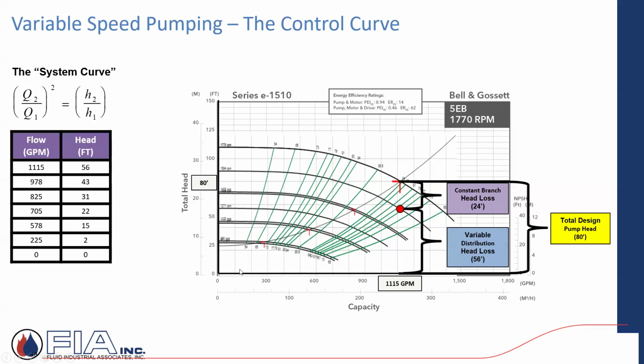So you start doing the math and saying, here's that system curve. We talked about it before, system 5, scale 5, I should say, or you can just do that little math equation, but you're plugging in different flow rates saying, hey, here's my design, 1115 at 56 feet. Why aren't I doing 80? Because I want to discount this constant pressure drop on the control head of the terminal unit. I need that all the time.